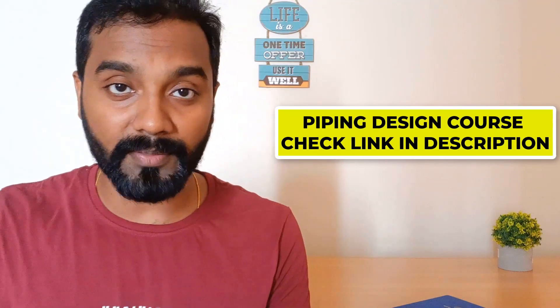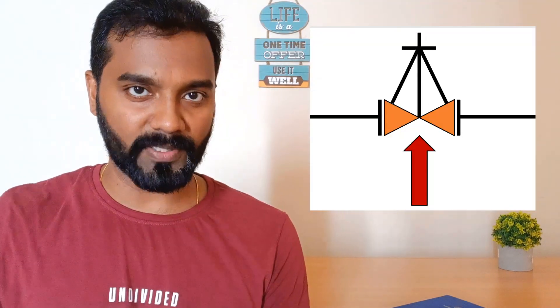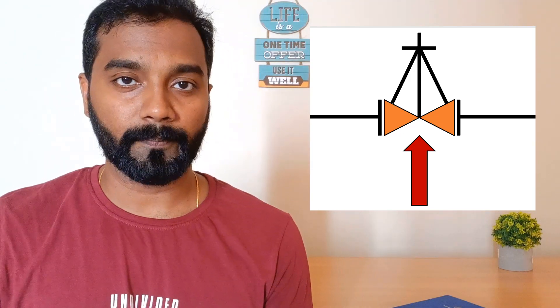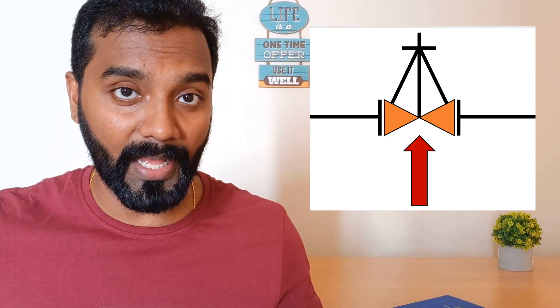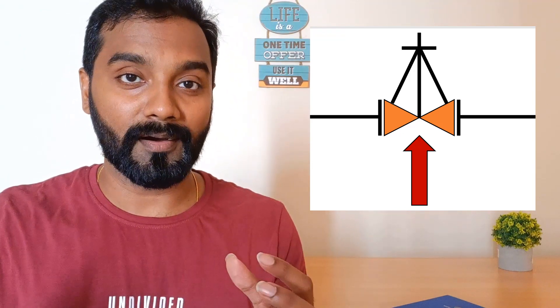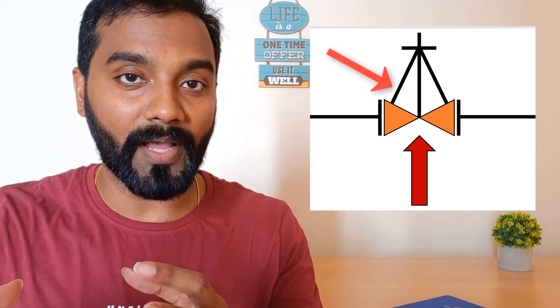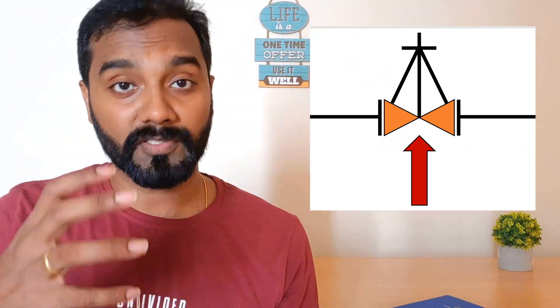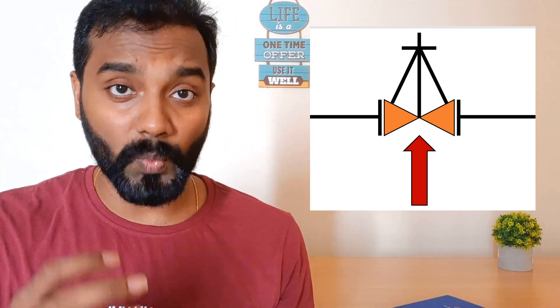Now let's move on to point number four: can we provide support below the valves? Valves are dead-weight items — the weight of a valve is more than any other item in the piping, incomparably more than flanges, instruments, or fittings. So can you directly put a support below the valve? If you do, the valve becomes stationary and the load of the piping acts on the flanges of the valve, causing huge fatigue and stress over the valve body. If the valve cracks, it is a huge loss because the cost of a valve is more than any other part of the piping.